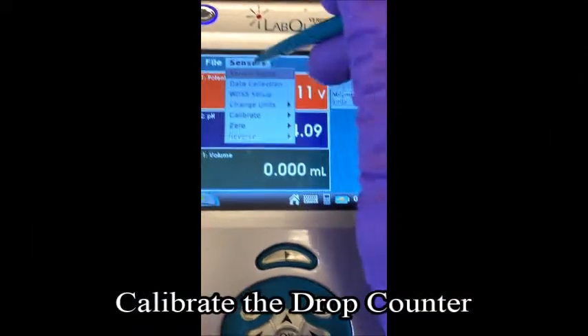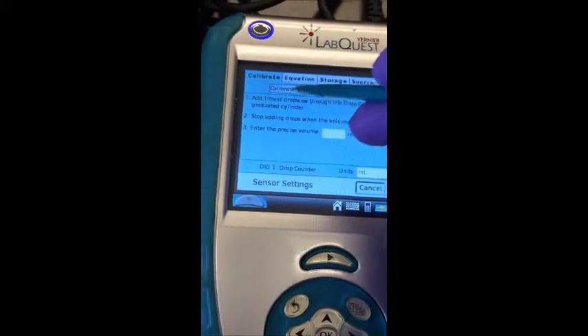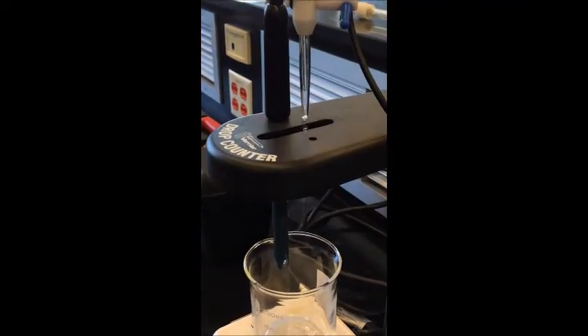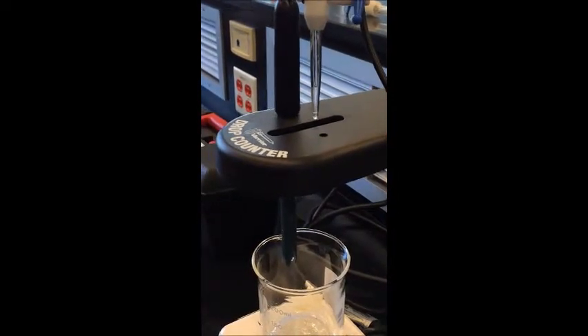Next, you will need to calibrate the drop counter. On the LabQuest, select Sensors, Calibrate, Drop Counter, press Calibrate now. Fill the burette with water, and then you can start dropping at a rate of 1 drop a second. Let the LabQuest count the drops. Calibrate until about 5 milliliters of water. Once it is done calibrating, enter the volume for 5 milliliters and then press OK.